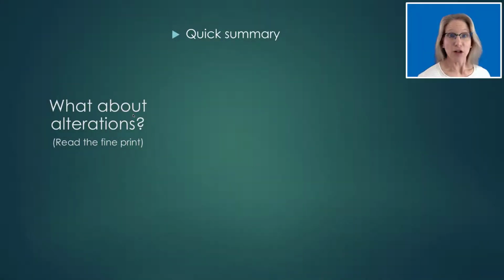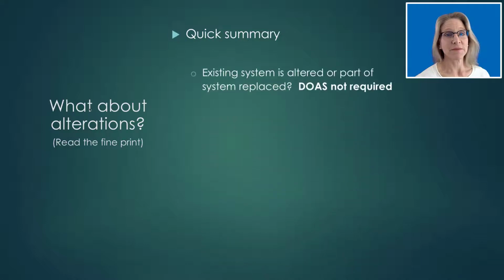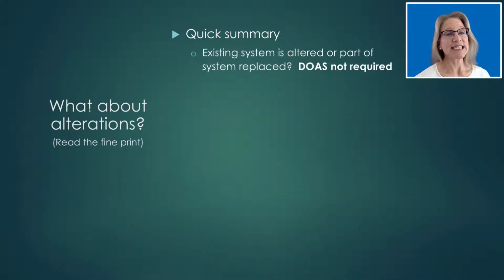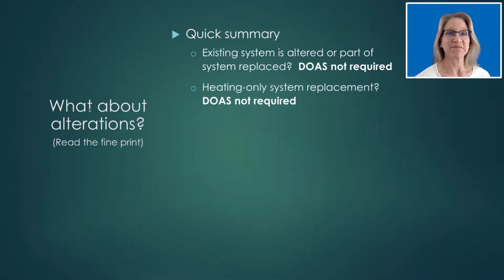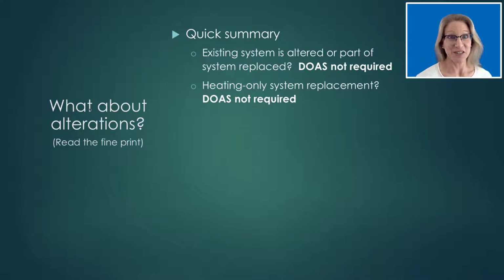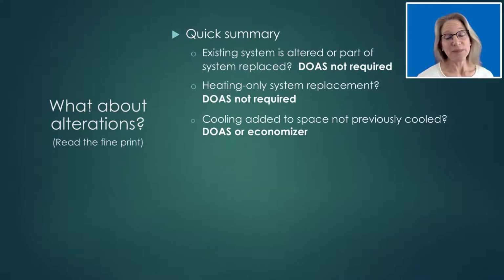So what about alterations? For a mechanical alteration project, whether DOAS is required depends on the condition prior to and after the alteration. If the project is an existing system that is being altered, or just a part of the system is being replaced, then the DOAS requirement does not apply. And if it's a heating only system, then DOAS is not required in that situation as well. If cooling is being added to a space that was not previously cooled, then you can comply either via DOAS or you can comply via the economizer requirement.